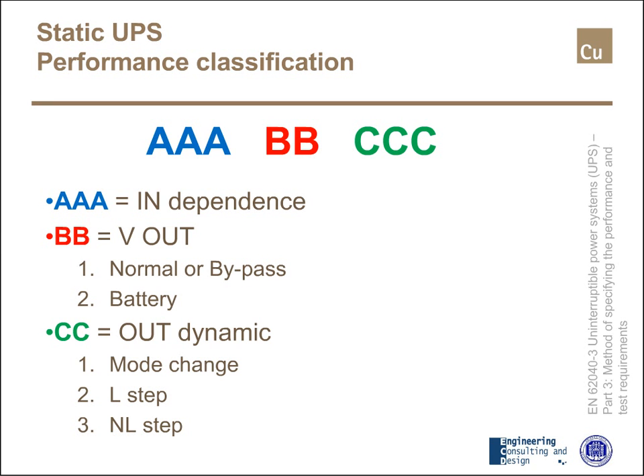The first three letters, AAA, shown in blue, describe the dependence of the UPS output from the input. The red ones, BB, describe the quality and type of the output — the first one in normal operation or bypass, and the second one in battery operation. If we have an S, this means the output is sinusoidal. The last three letters, CCC, in green, describe the dynamic behavior of the UPS output with reference to change of mode, a step of linear load, or a step of non-linear load.